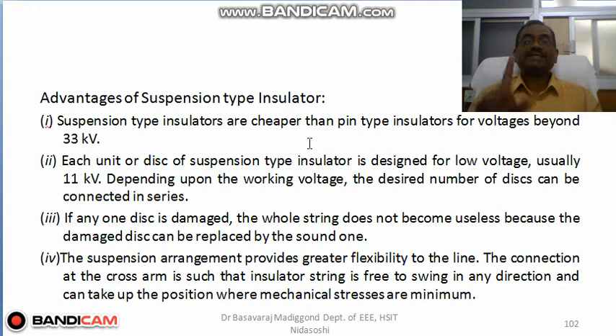If any one disc is damaged, the whole string need not be replaced. So we can replace the damaged one by the standby one, the second good one. Okay. The suspension arrangement will provide a greater flexibility to the transmission line. The connection at the cross arm is such that the insulator string is free to swing in any direction and can take up a position where mechanical stress is minimum.